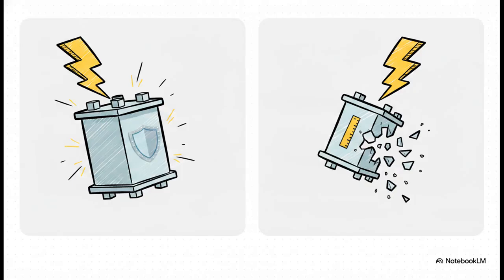This leads to a really critical engineering distinction. You have to use the right equipment. Protection class instrument transformers are specifically designed with larger cores to handle these high current, high distortion conditions without saturating. Metering class transformers, on the other hand, are highly accurate for normal daily power flows, but they saturate so easily during a fault. Seriously, using a metering class CT for protection duty is a massive career-limiting design mistake. It'll saturate, the relay will underread the fault, and it just won't trip.